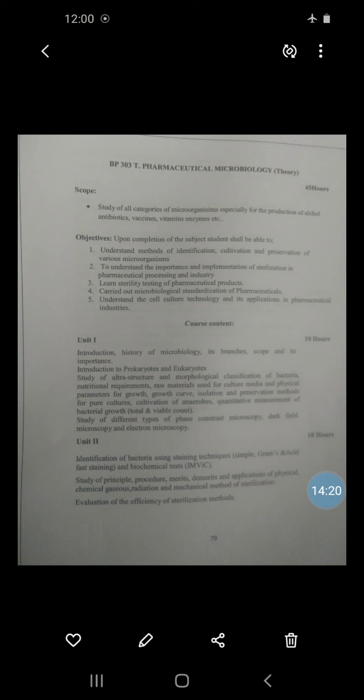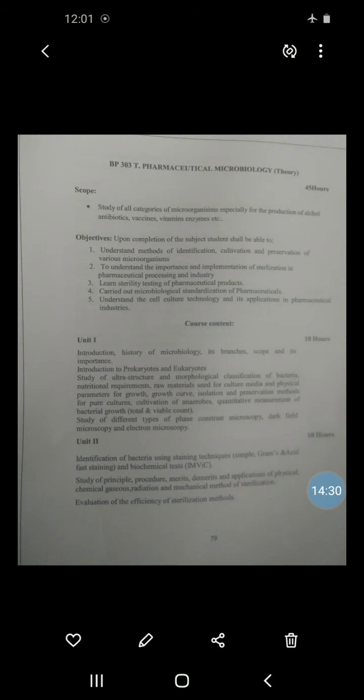And generally 40 to 50% moisture is necessary to have the maximum efficiency of ethylene oxide as a sterilizing agent.